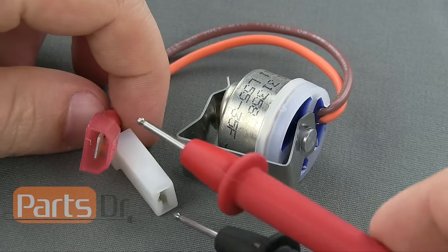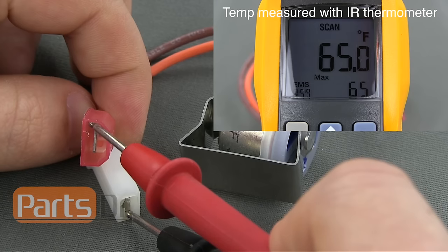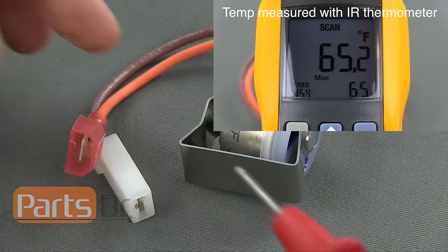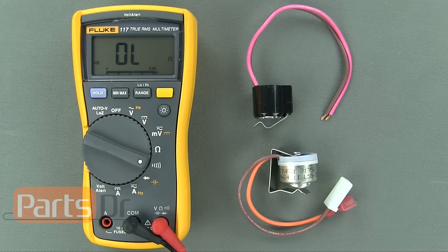While the thermostat is warmer than the opening temperature, the thermostat should not have continuity and the meter will not make any noise. In this case, this thermostat should not have continuity if it is 55 degrees Fahrenheit or warmer.